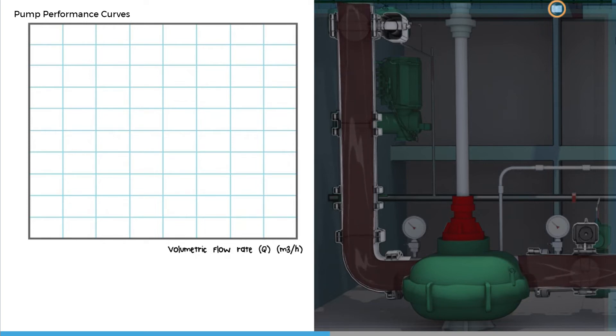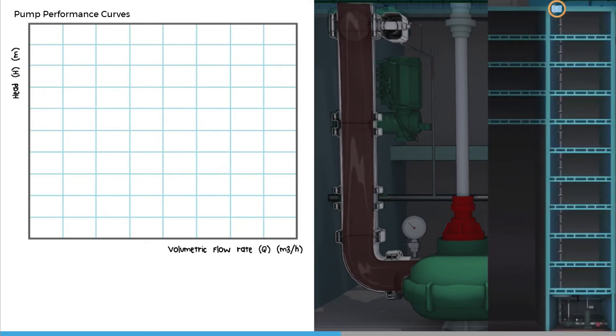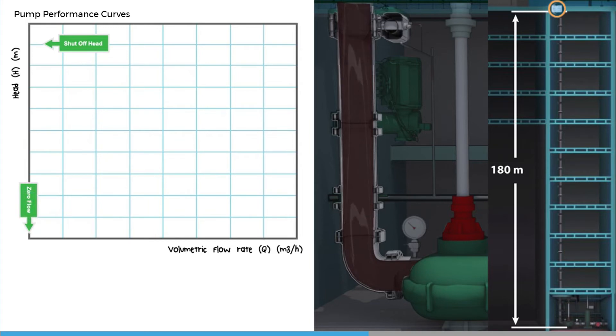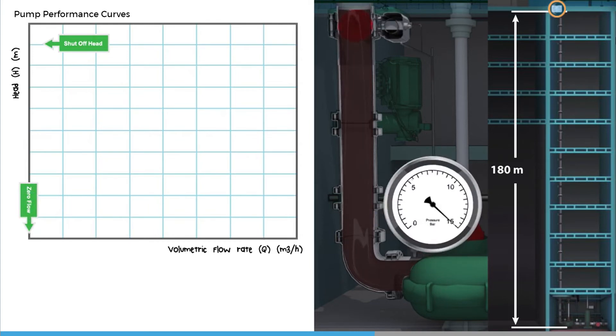The y-axis represents the head in meters. We give this the letter H. The maximum head that a pump can generate occurs when the flow is zero. We call this the shut-off head, and it is equivalent to what would be seen on the pump discharge pressure gauge if the valve was closed against the flow.